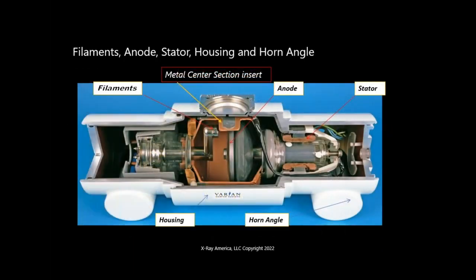All this area is filled with dielectric oil. In the smaller tubes, the heat radiates from the tube into the oil to the housing. You're not putting that much energy into it. When you get to a million heat unit tube, typically you have a heat exchanger. So you have tubing connected to this, and it goes to what's usually an oil-to-air heat exchanger. So you have the oil actually being pumped through the heat exchanger. In CT, you always have a heat exchanger because there's so much more heat.